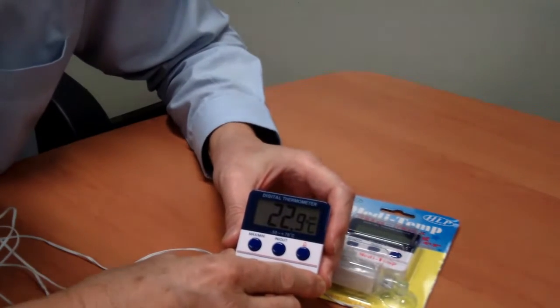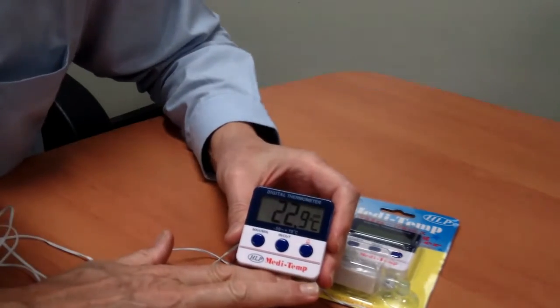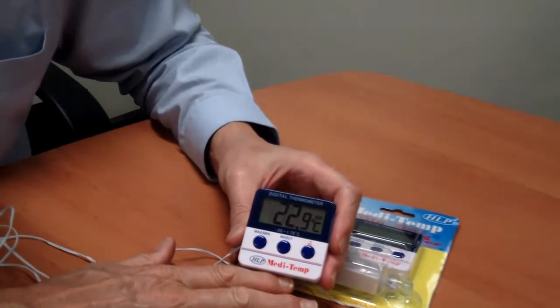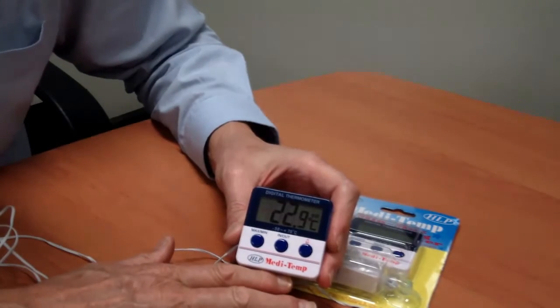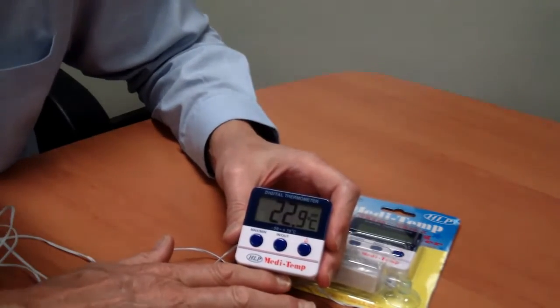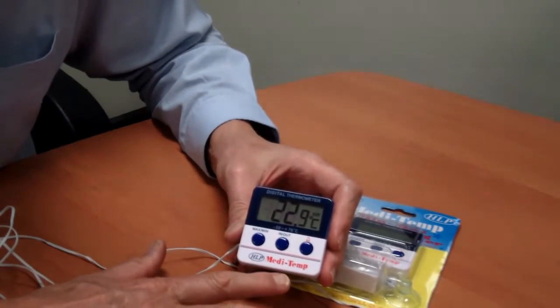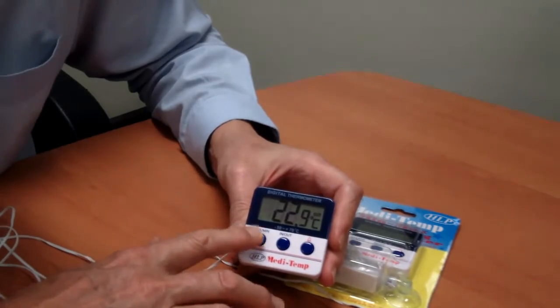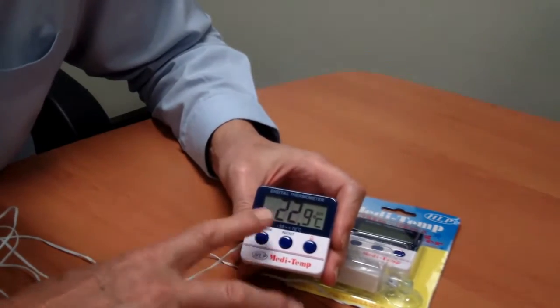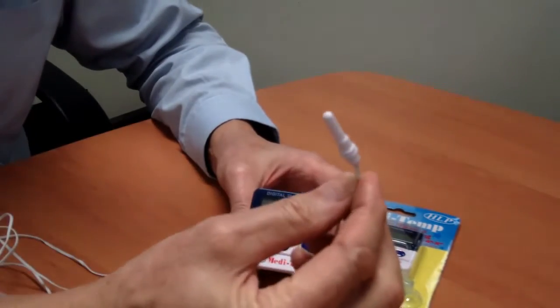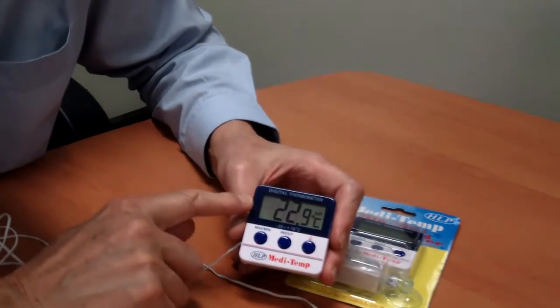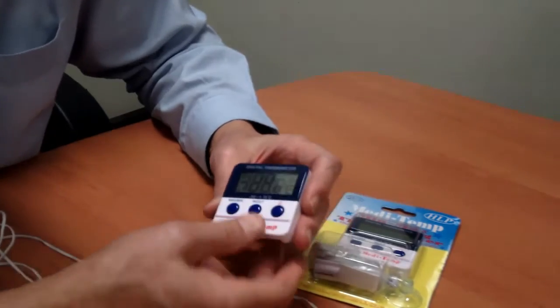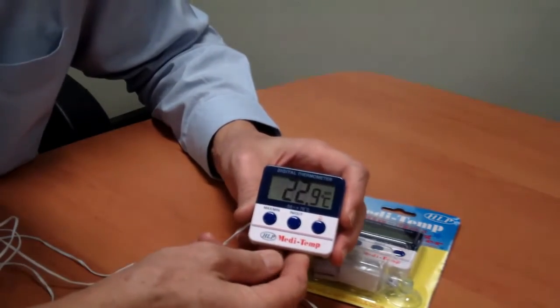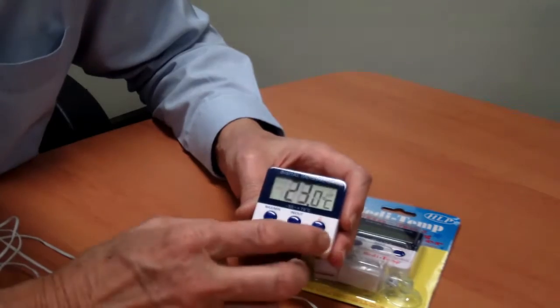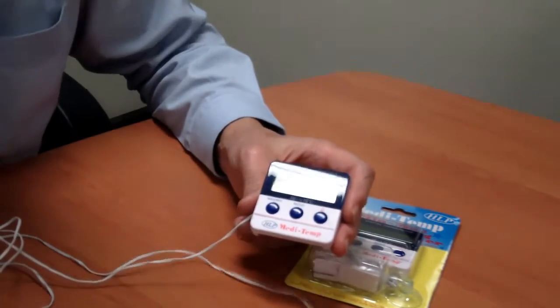Alright, so this is the face, a close-up of the Medi-Temp. The Medi-Temp is used for any sort of fridge monitoring. It can be used for vaccine fridges, food fridges, whatever. And it's got a fully adjustable temperature alarm, and it's also got a minimum maximum display. It's got 2 temperature sensors, one built into the unit and one built into the outside probe. So with this unit, when you first get it, you put the batteries in, one battery in the back. It's a AAA battery, comes with it. You close the back, and then it just reads.